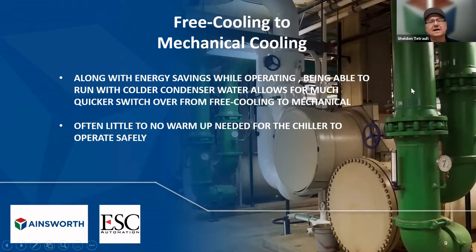So another thing that comes up is free cooling to mechanical cooling, and the switch over and how you pick that number. This is kind of an expansion again of the colder condenser water. One of the advantages of new machines is that you do not need the warm-up loop like you did in the past on the cooling tower. So if you were switching from free cooling, in the past you would have to warm up the tower sump so that it would be at least in the 68 to 70 degree Fahrenheit range before you would enable the chiller.